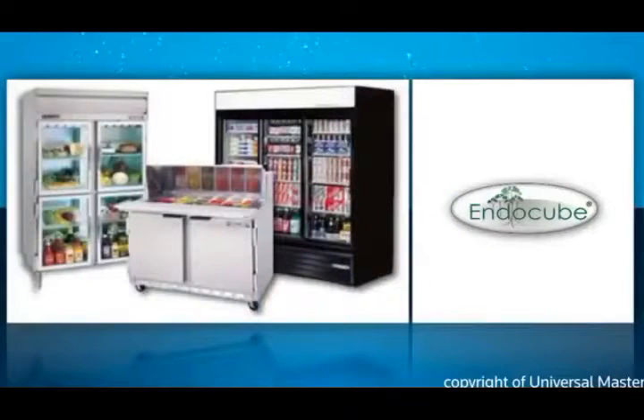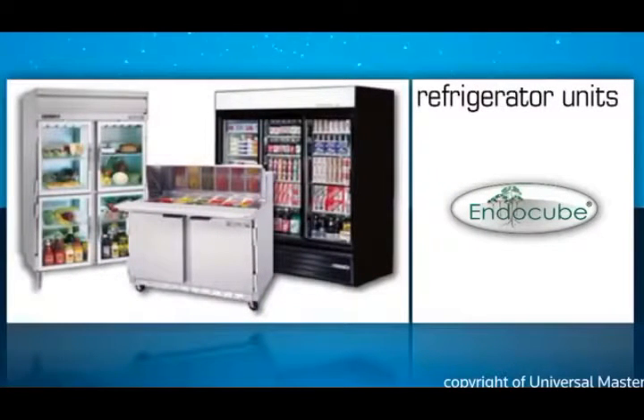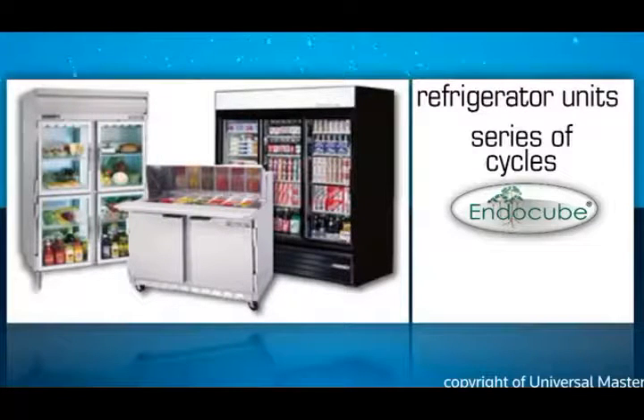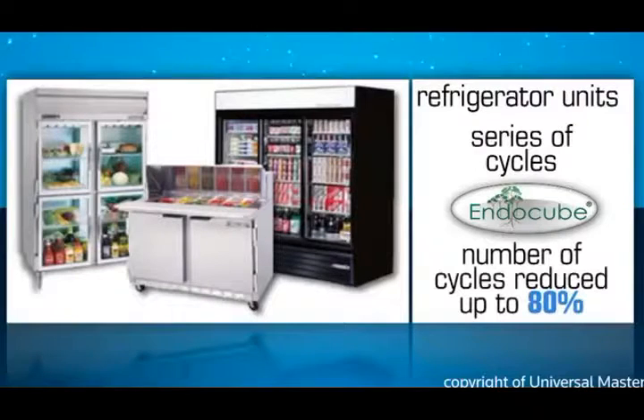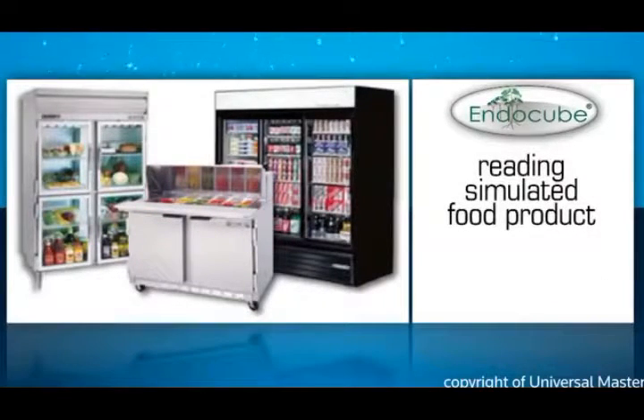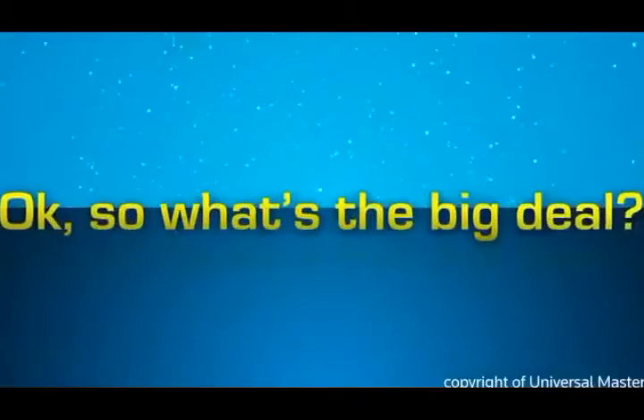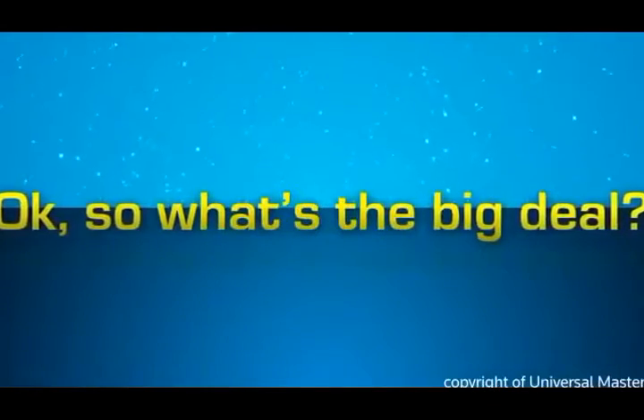Of course it does. Refrigeration units work on a series of cycles, with a thermostat probe using air temperature to trigger the on-off cycles of the compressor. With Endocube installed, the number of compressor cycles is dramatically reduced. Why? Because now the probe is reading the simulated food product inside Endocube, which responds to temperature changes far more gradually than air. Okay, so what's the big deal?